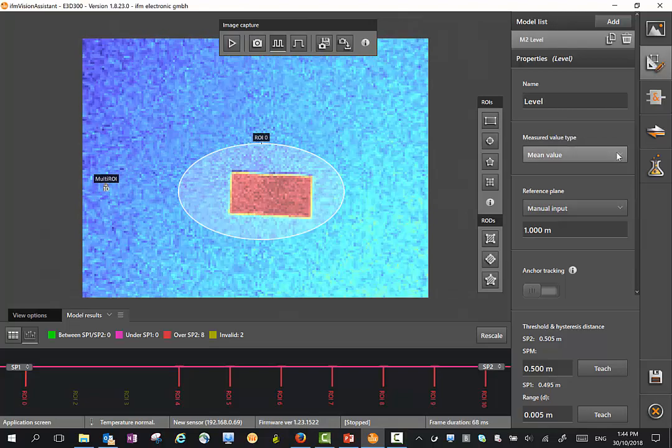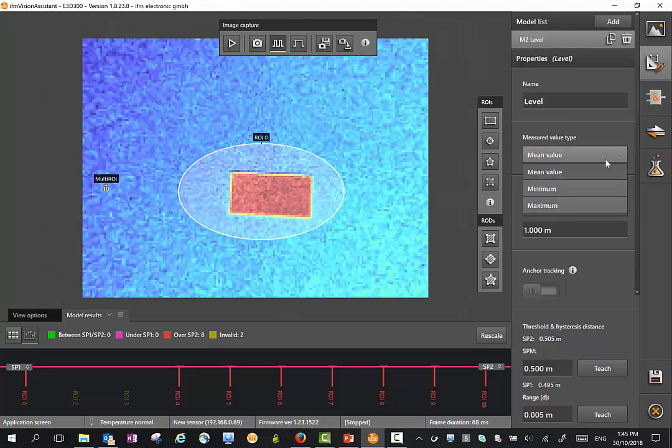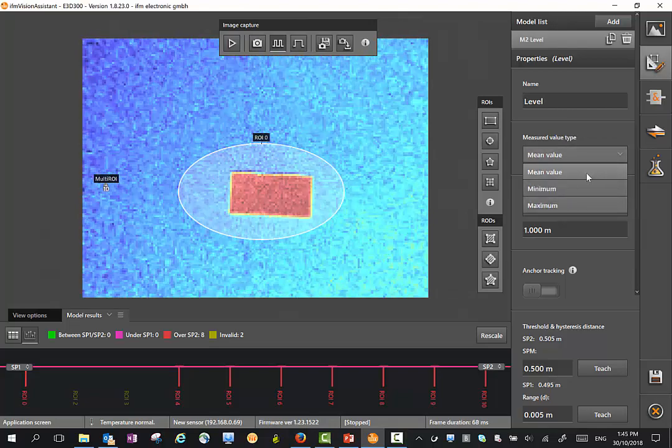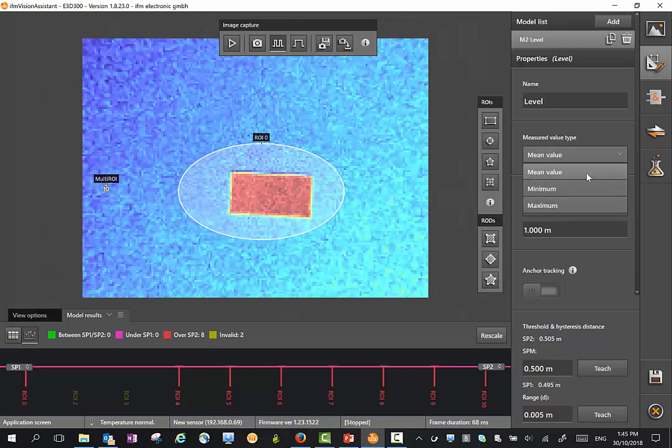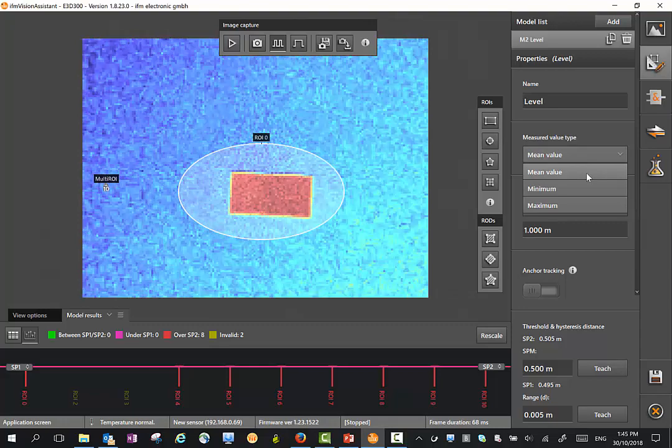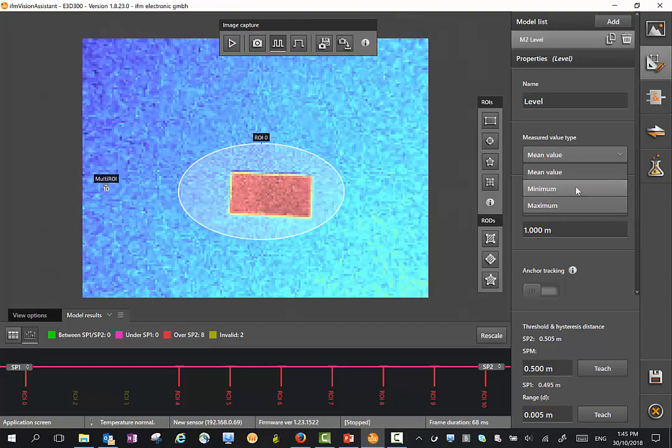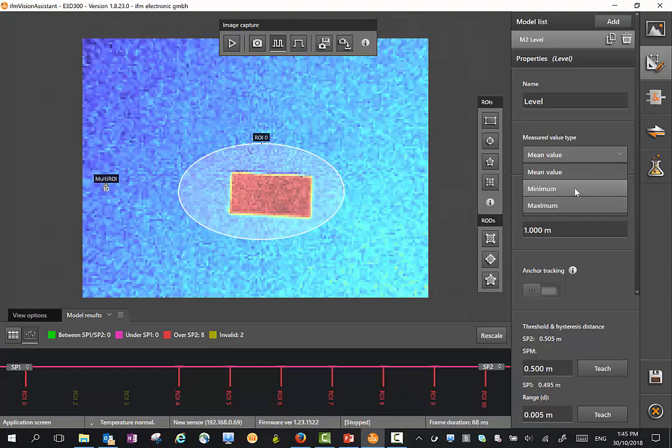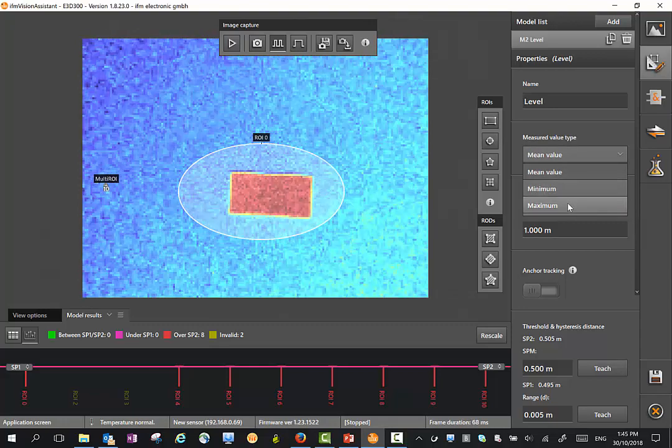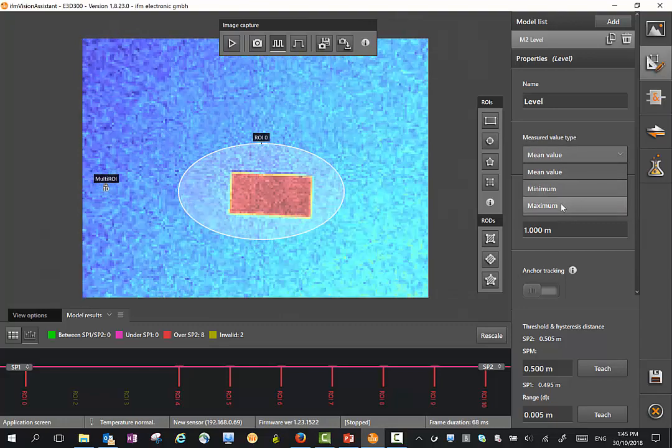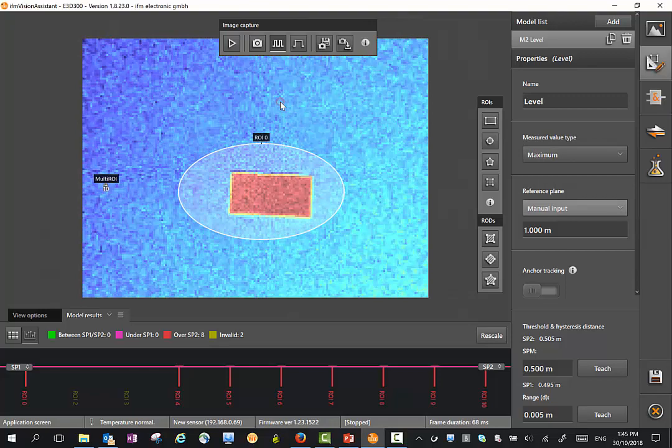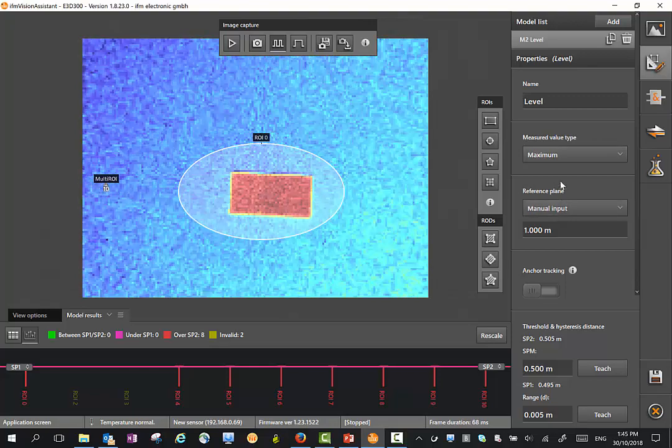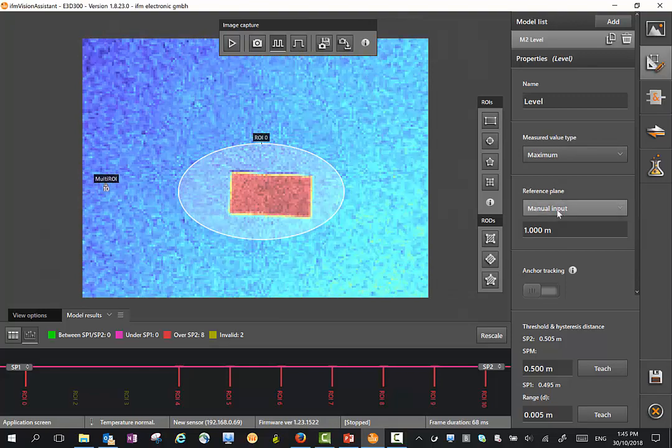The measured value type can be the mean value where we have an average of the pixels in the region of interest. We can look at the minimum value or the maximum value. For level applications, the maximum value can be a good way to work.